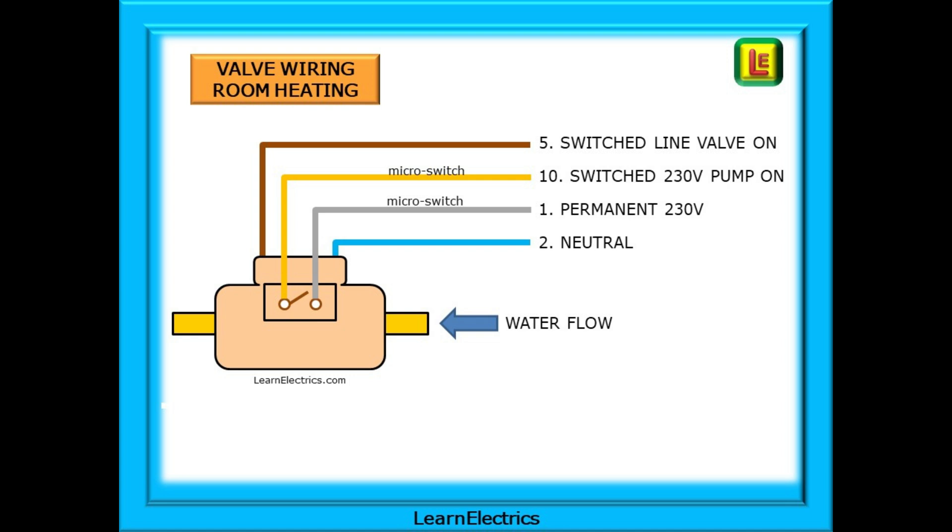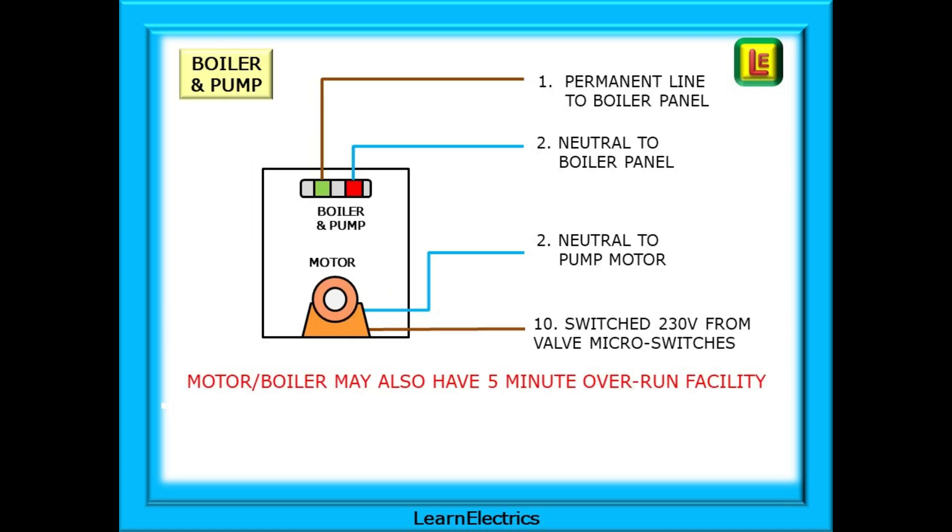As the valve rotates it will close the microswitch inside the valve body. The microswitch has a permanent 230 volt connection on the grey wire and when the switch closes this voltage will pass through the switch and go to the pump motor. The 230 volt output from the valve microswitch will turn the pump motor on as there is already a neutral at the motor.